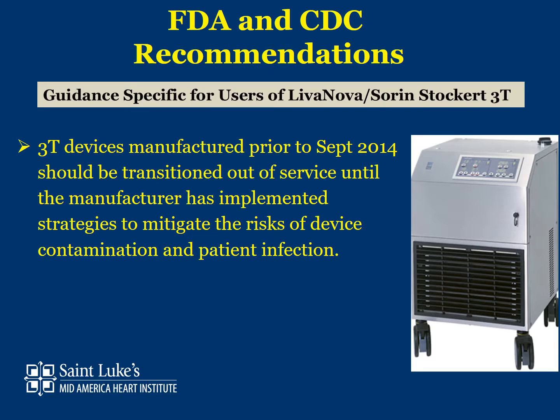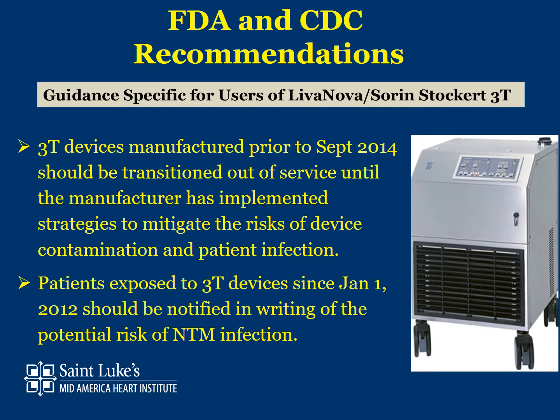There are some specific recommendations for users of the 3T device from Sorin. 3T devices manufactured before September of 2014 should be transitioned out of service until the manufacturer has implemented strategies to mitigate the risk of device contamination and patient infection. It's my understanding that Sorin is currently working with the FDA on a strategy like this.